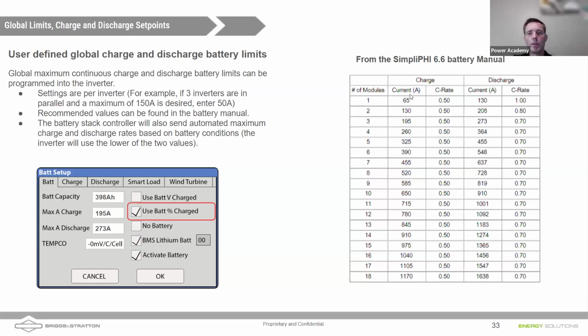So we want to make sure that our battery bank, these currents here are DC currents. If you want to get a rough idea of how much power is coming out of that, the battery's operating nominally at about 50 volts. So if we take the 200 amps times 50 volts, we get a little under 10,000 watts of power. So when you're programming in that maximum charge and discharge rate to the inverter, that's in DC current.